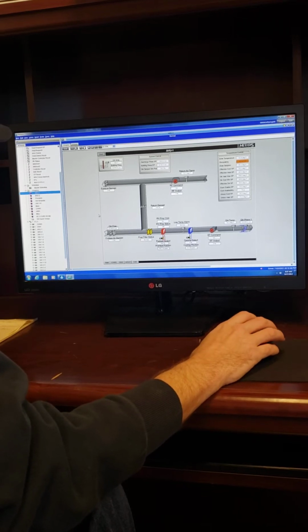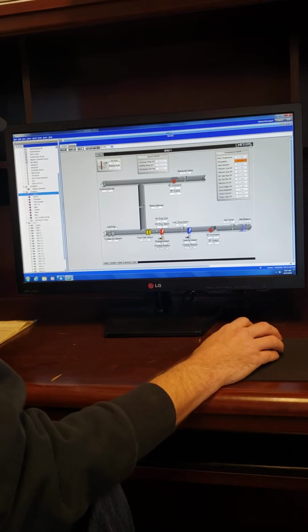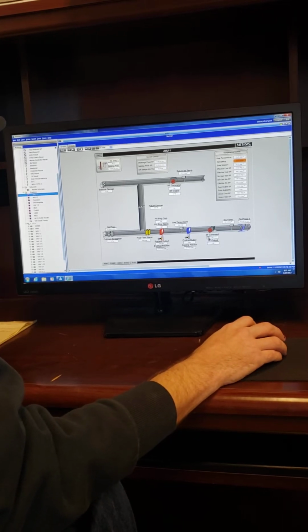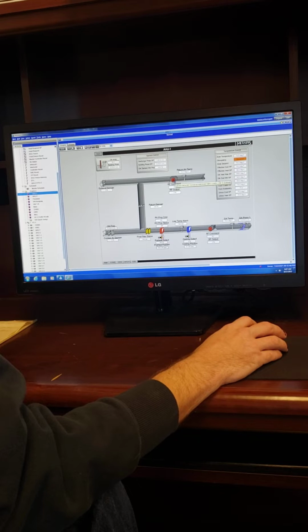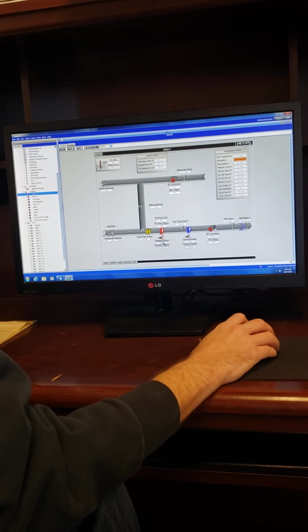One thing we found on air handler number 2 that is now currently happening on number 1 is we have a command on for our fans and our status is off. Normally these would be spinning green and have an output and have some pressure and all that.